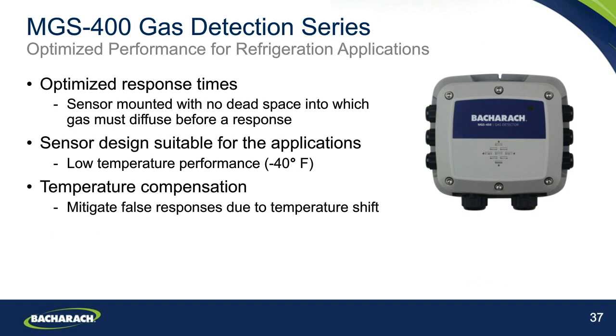The performance of the MGS-400 series is absolutely focused on being optimized for refrigeration applications. Response times here are optimized by mounting the sensor in a sealed manner at the front of the system, right where the gas is going to permeate through to it. That means there's no dead space into which the gas must diffuse before a sensor gives a response. If you were to look at a system that is a sensor open within a housing, that gas has got to start to fill up that whole enclosure before we're going to get an accurate response. This is as close really as we can get to having a raw sensor open in the atmosphere. But of course we've got the protection here of the IP ratings of the system, and the responses will be quick.